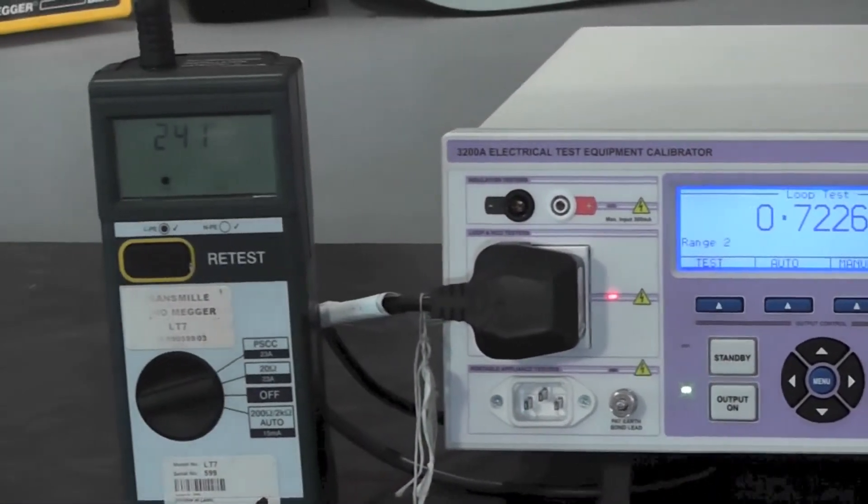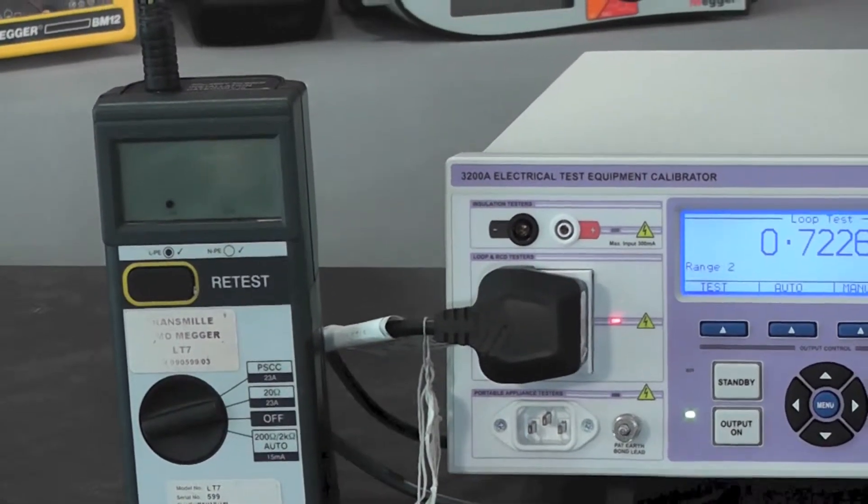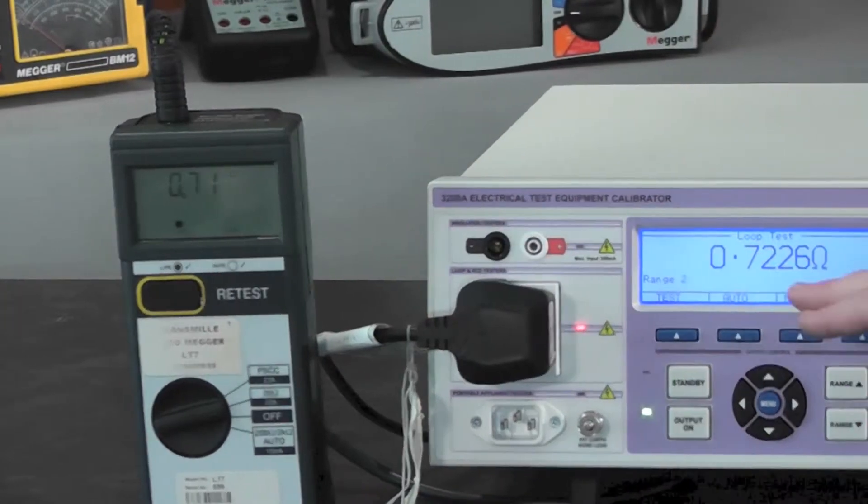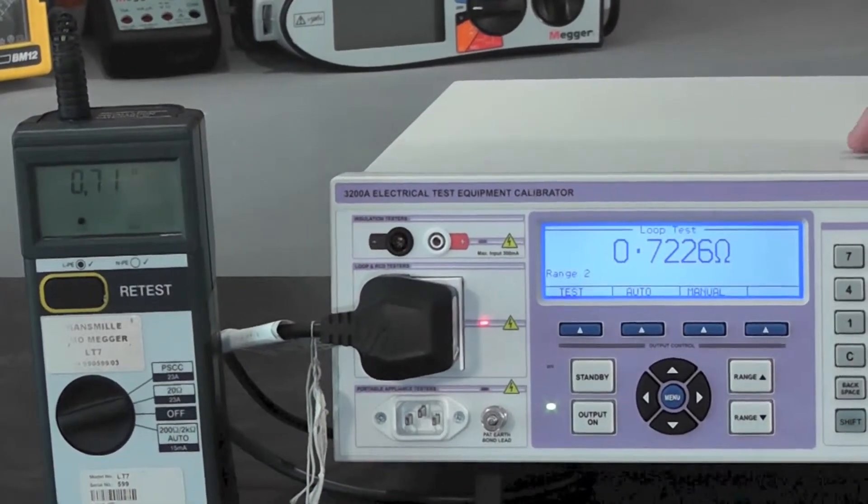After waiting for the loop tester to initialize, compare the recorded result from the loop tester adapter against the indicated value on the 3200A.